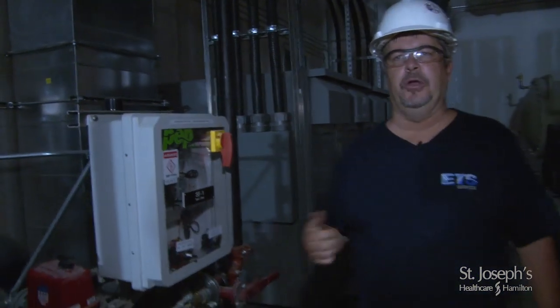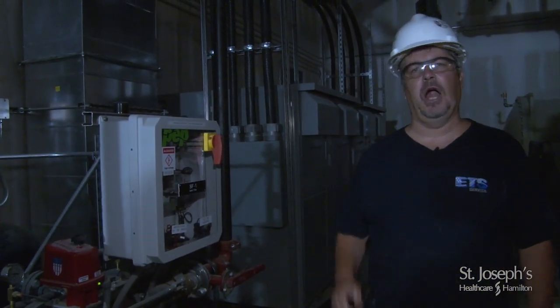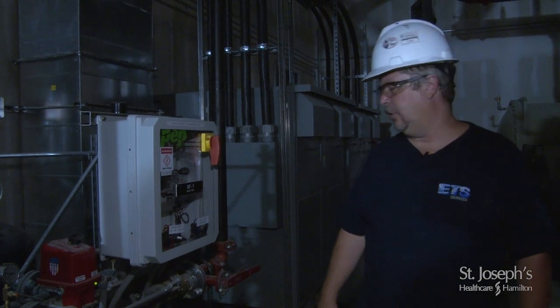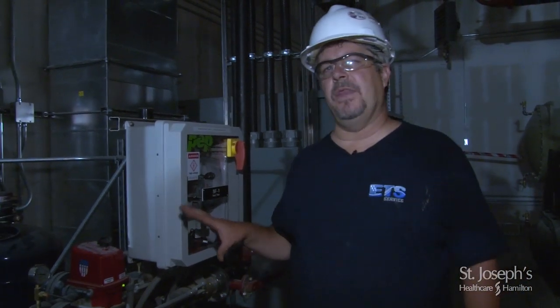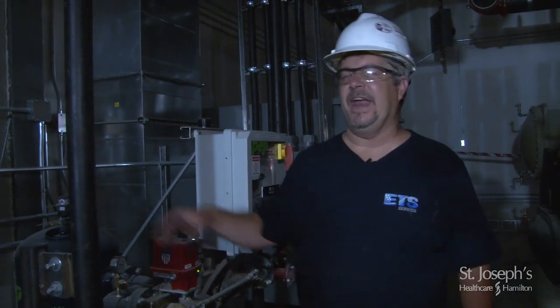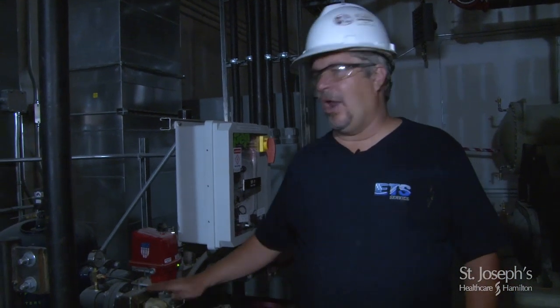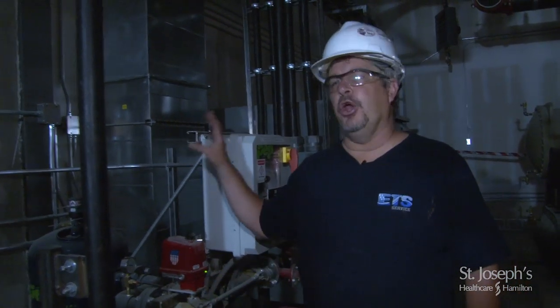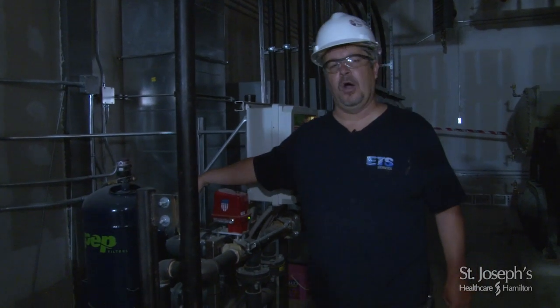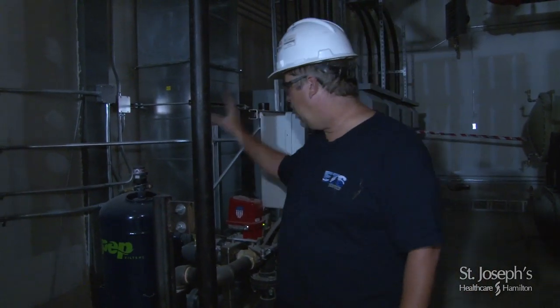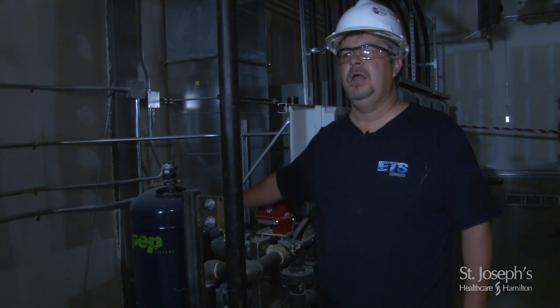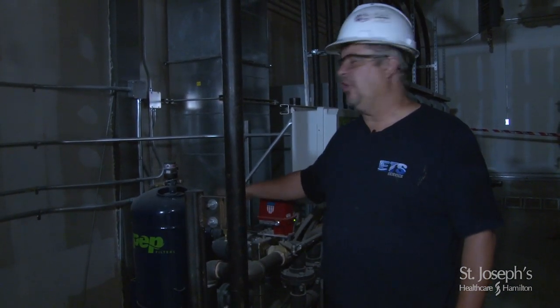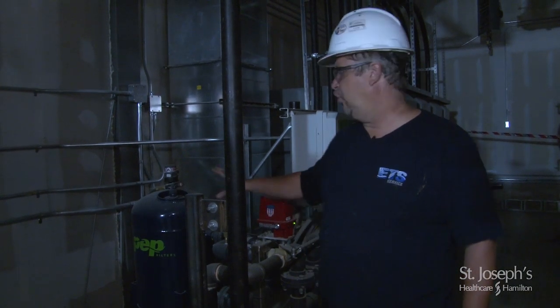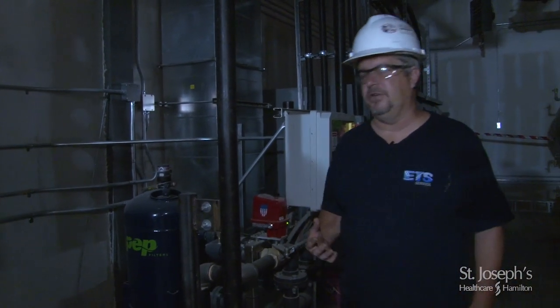Again, this unit is fully automatic. There really is no reason for you to have to do that, but the option is there if you feel the need to do it. The last thing on this filter assembly is the actual filter media itself inside that tank. When this unit was put online earlier this year, brand new filter media was installed in the tower. There was also a spare set of the media sent with the tower, so that the next time you need to do the maintenance, you have it to do.